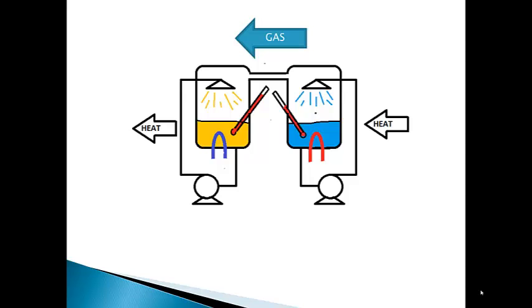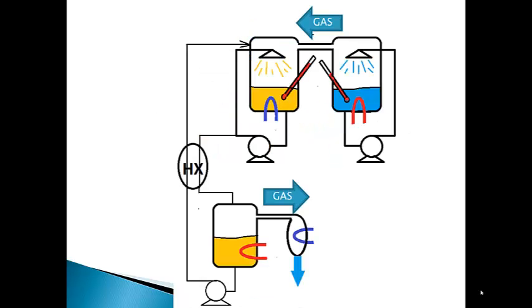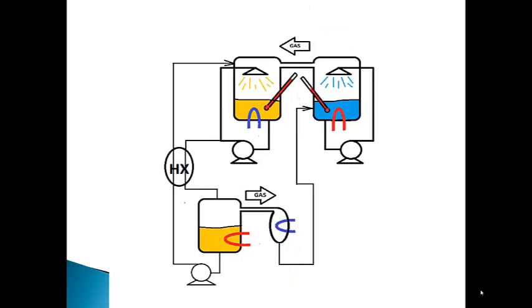That is until we add some equipment to make it operate continuously. You see, as the salt solution absorbs water vapor, it becomes more dilute. We must add a device to reconcentrate the brine by removing the absorbed water. This can be accomplished by distillation. A portion of the dilute brine enters a still and is separated into a stream of product water and concentrated brine. The concentrated brine is put back into the absorber vessel, and the water product can be sent back to the evaporator to complete the water circuit.